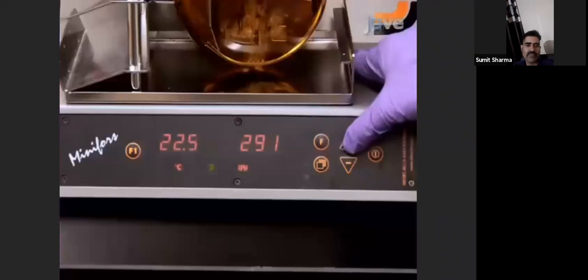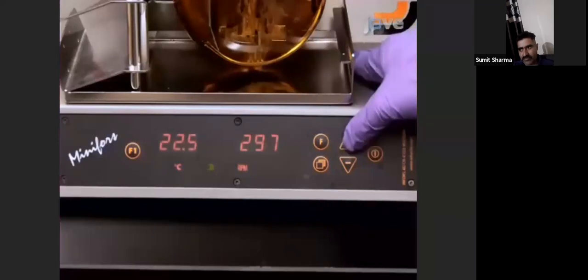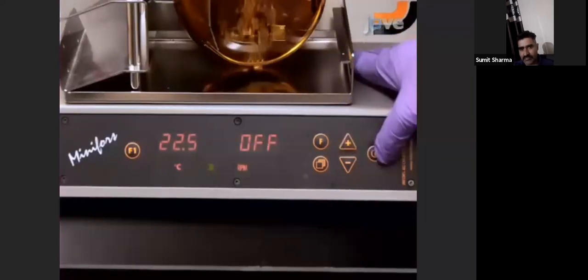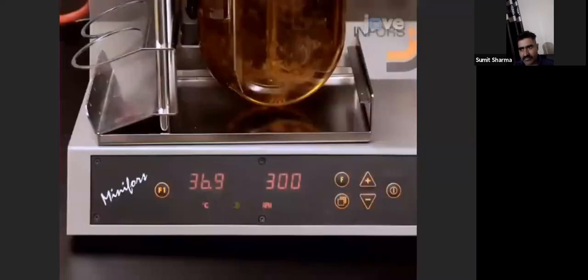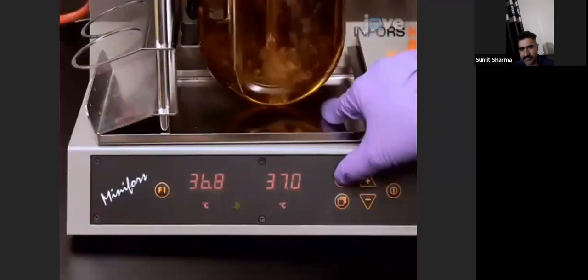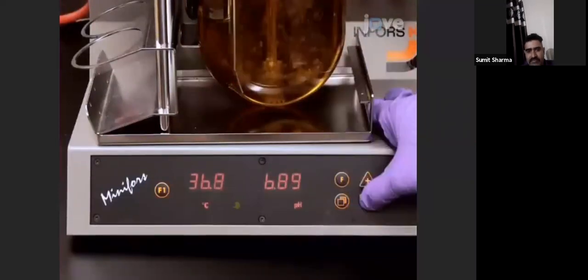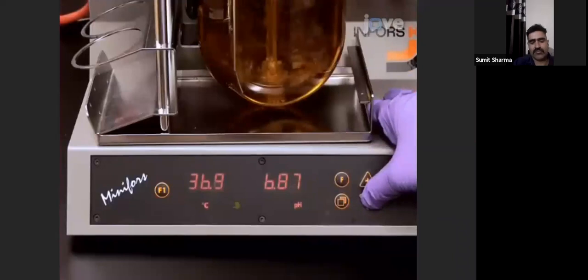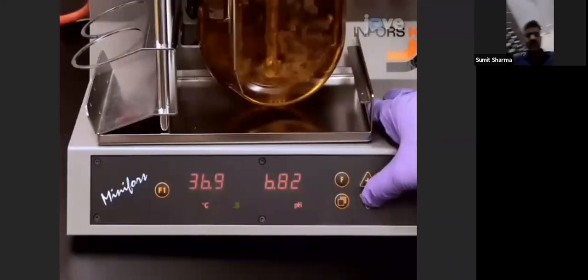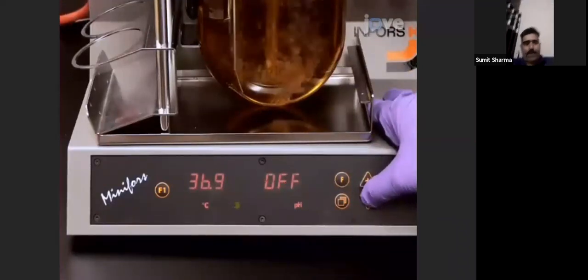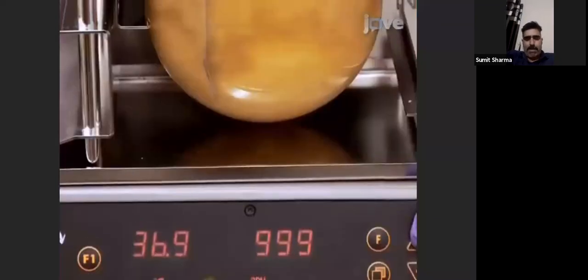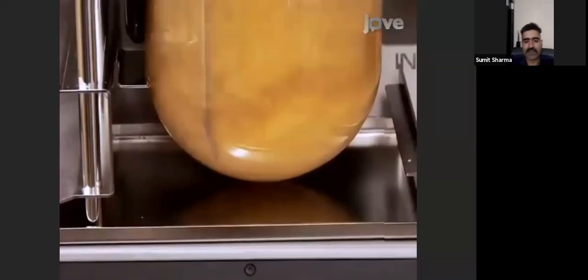Bubbles should appear at the bottom. Scroll to the agitation parameter and set to 300 RPM. Press Enter to turn on the agitation. Once the temperature has reached 37 degrees Celsius, scroll to the pH parameter and set it to 6.8. Turn the pH control on by pressing the Enter button. Set agitation to the maximum speed of 1000 RPM for the run.